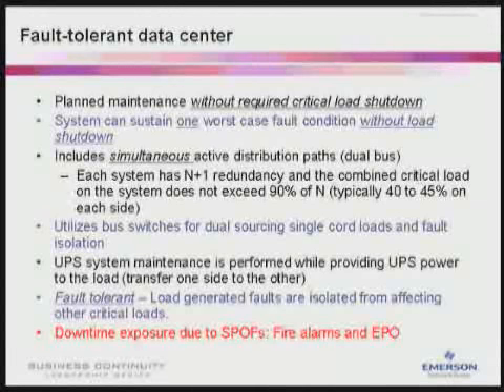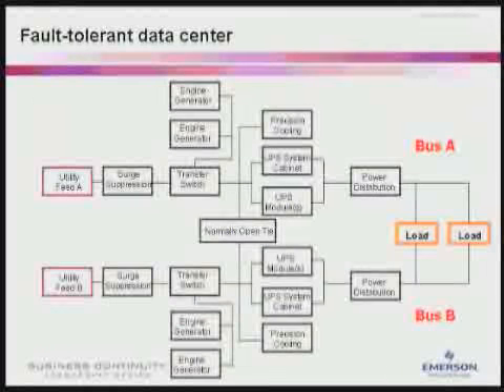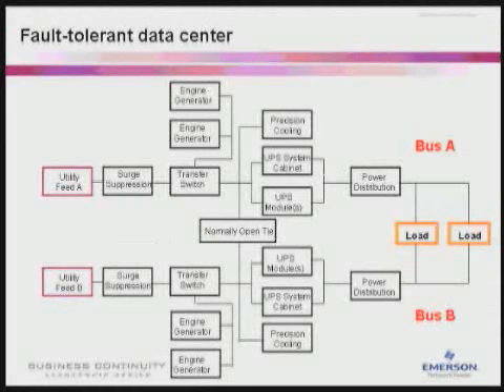Slide. Here's a one line of a fault-tolerant data center. Redundant feeds, redundant engine gen and transfer switches with precision cooling on the generator-protected sources, redundant UPS systems, dual critical buses to separate power distribution paths powering dual-corded loads.